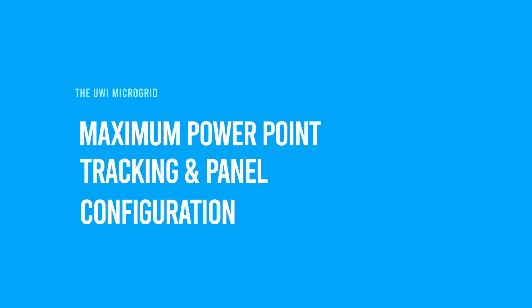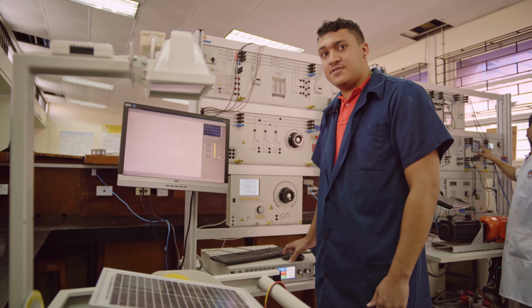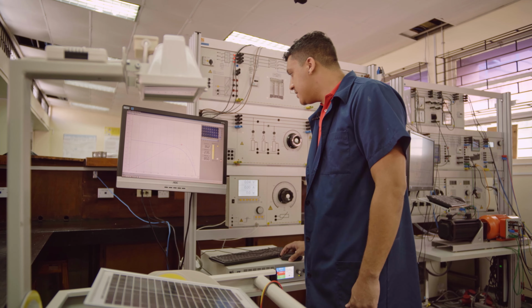Now we'll be looking at MPPT, which is maximum power point tracking, and as we change the irradiance, which is the brightness of the sun that is falling on the PV modules, we can see a change in the maximum power point at each percentage of irradiance. So right now we are at about 60%, and we're getting a DC voltage of 362 and a current of 2.35, which gives us a power of 850 watts.